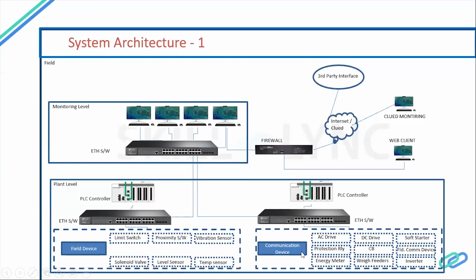Another type of input is for communication devices, such as AC drive, DC drive, soft starter, protection relay, circuit breaker, field communication devices, inverter, weigh feeder, energy meters. These communication devices may be on Ethernet protocol, or Modbus Ethernet, or Modbus RTU. But these communication devices are connected through a gateway. If Modbus RTU, it is connected through a gateway to the Ethernet switches, or if it is Ethernet, it is connected directly to the switches, or directly to the PLC controller. So this is your plant level, the plant level controller.